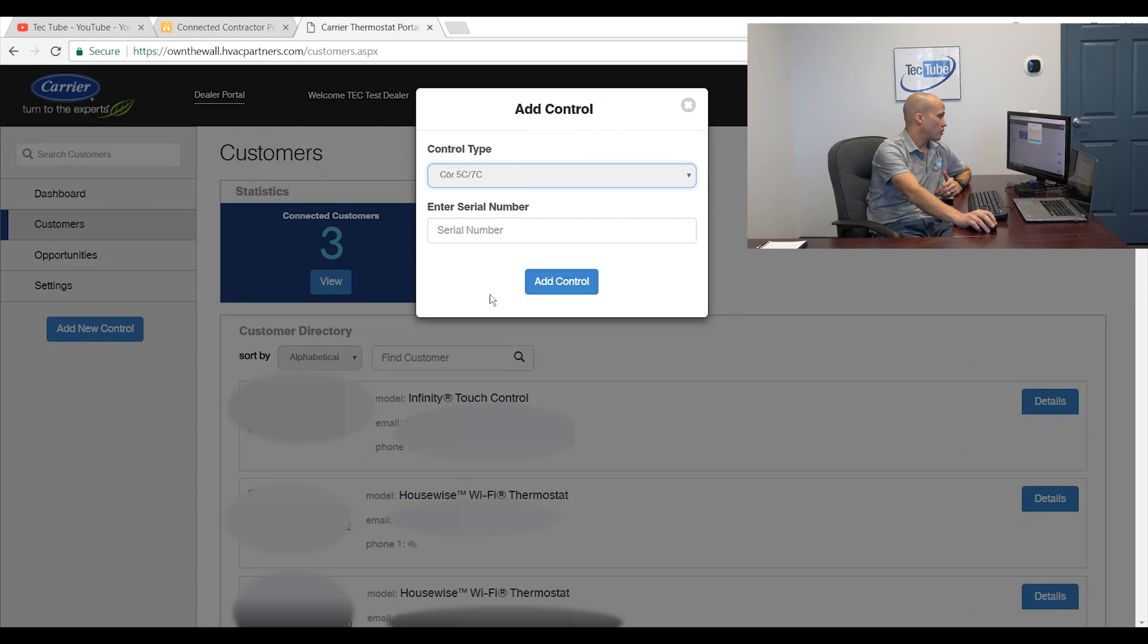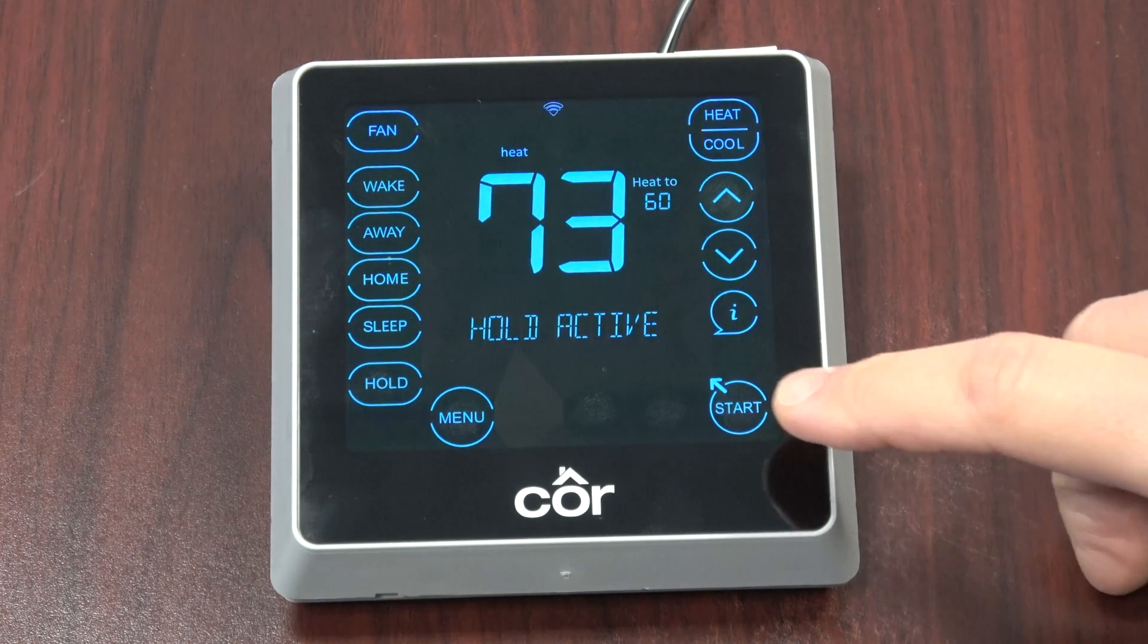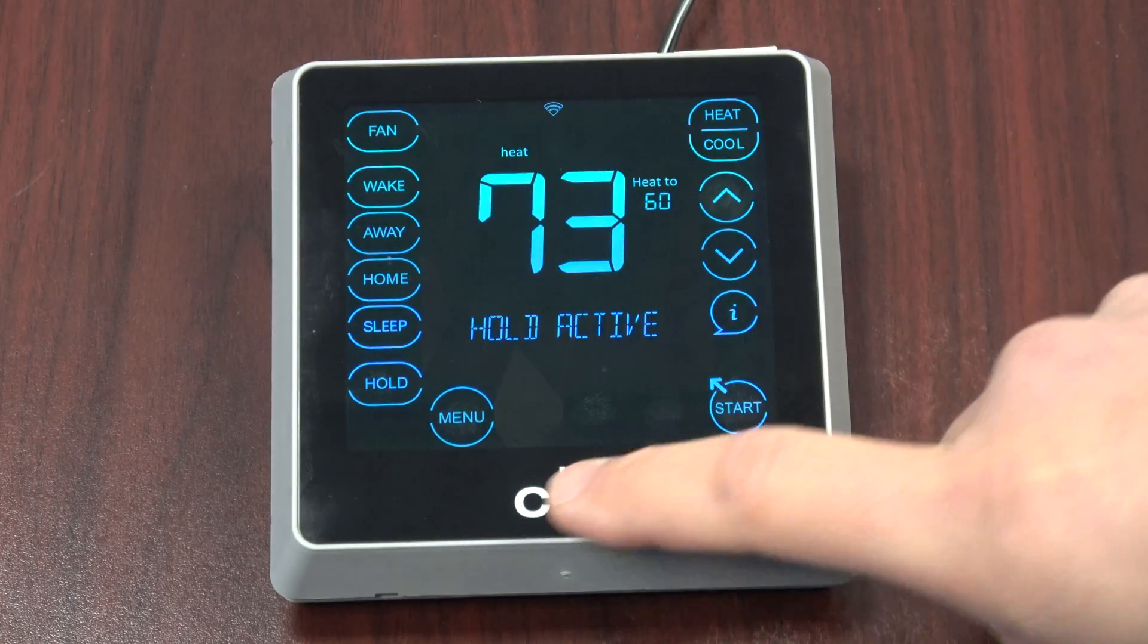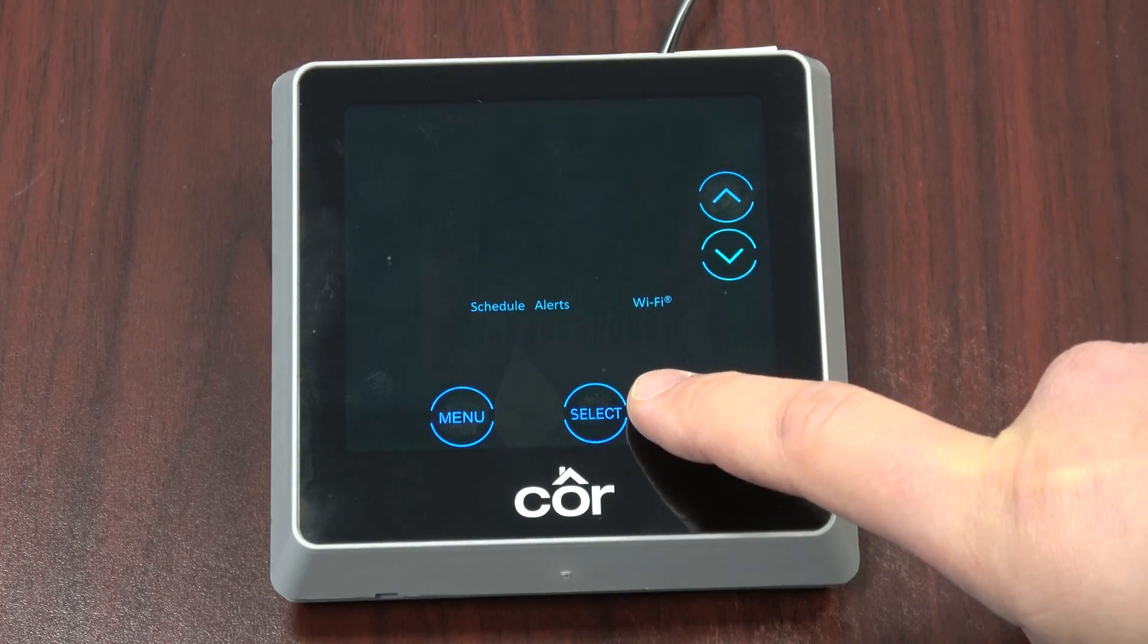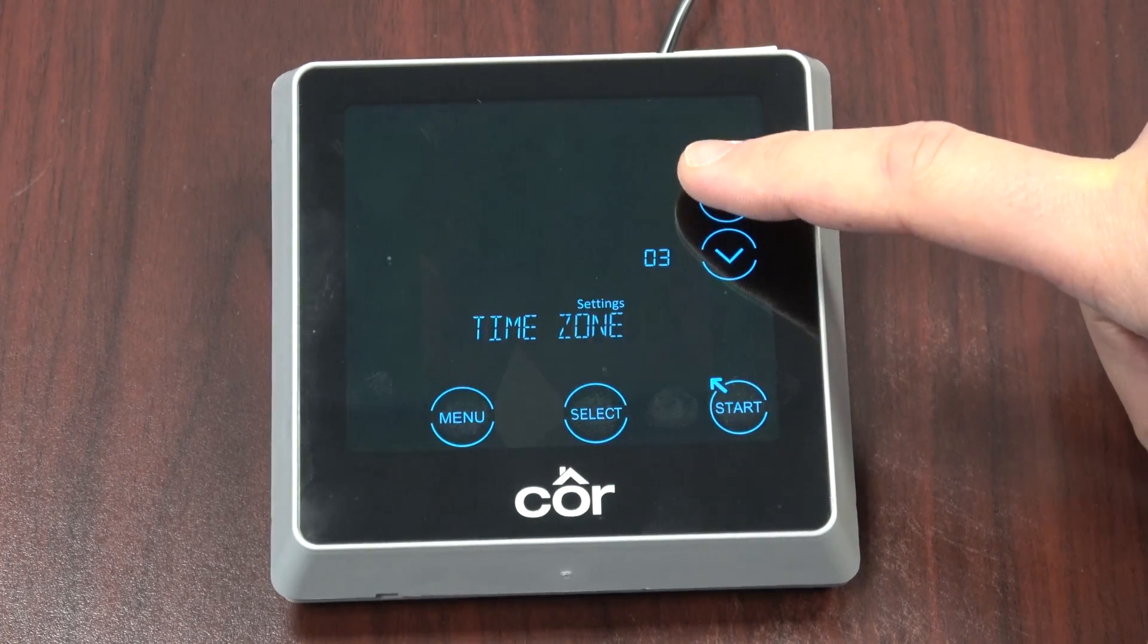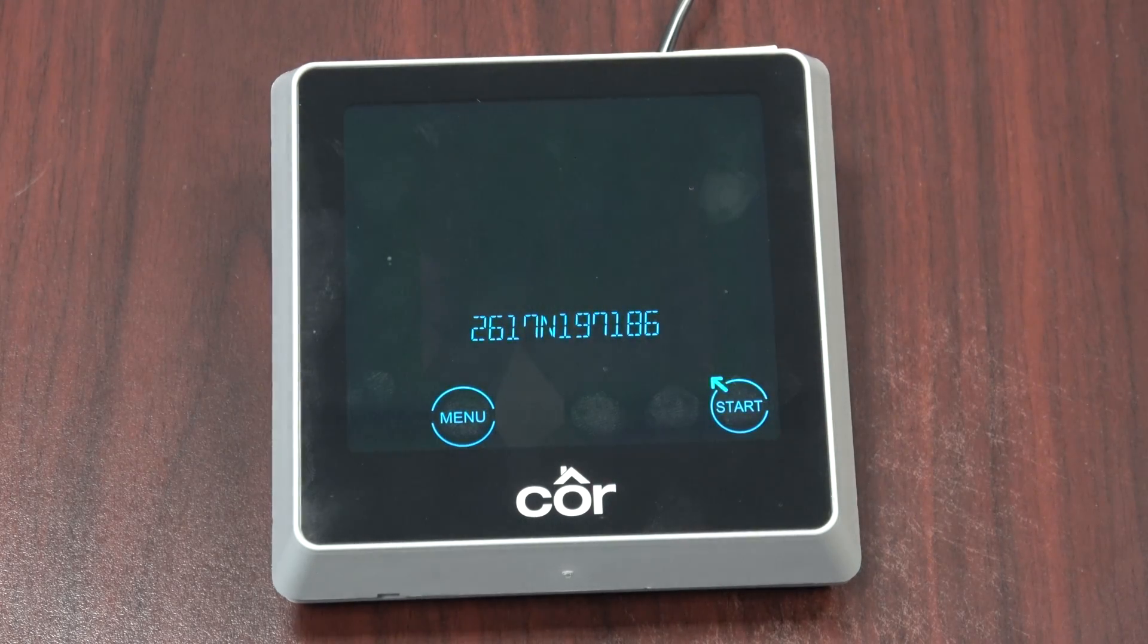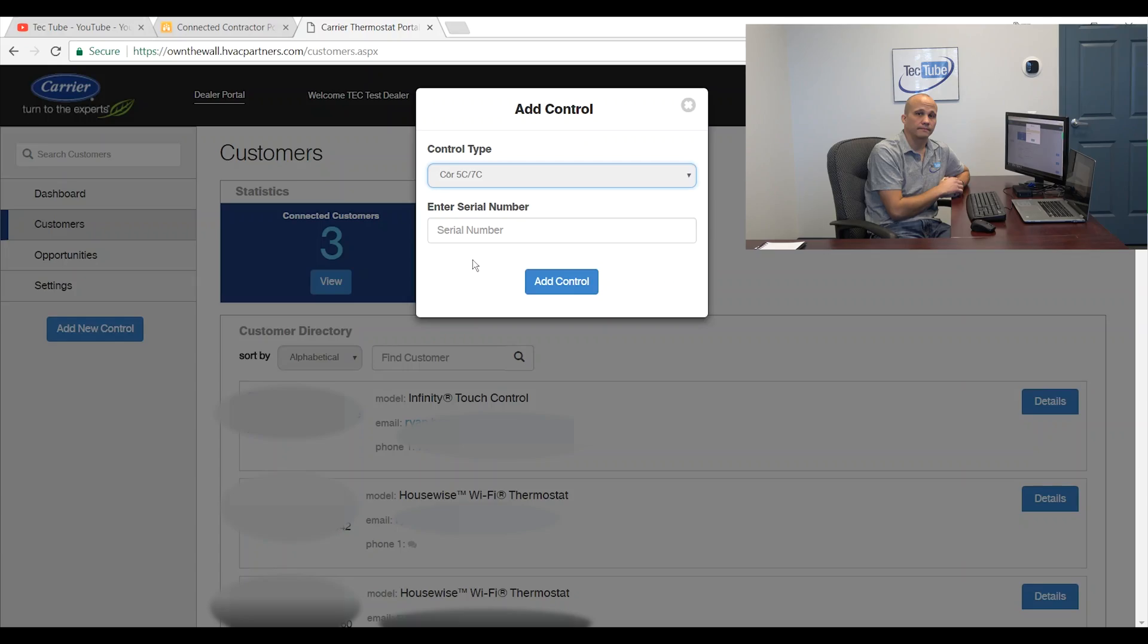The next one is the Cor 5C and 7C, which are the brand new Wi-Fi stats from Carrier and Bryant. So once again, I need the serial number. So let's go find those from the thermostat. On the Cor 7C, we'll press the start menu. And we'll press menu and we'll hit next until we get to settings. We'll select that. Now we're going to scroll over to 13 where it says serial number and then press select. And there's a number we're going to want to write down or take a picture of with our camera. And then I would add control.